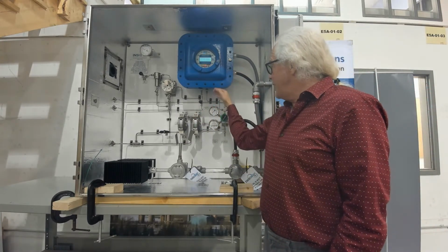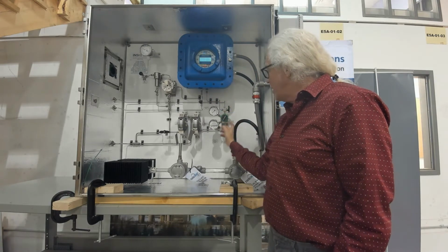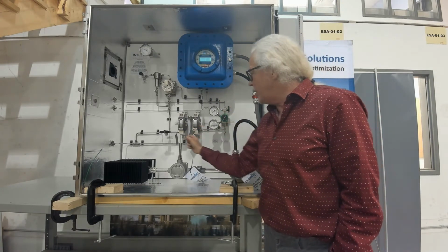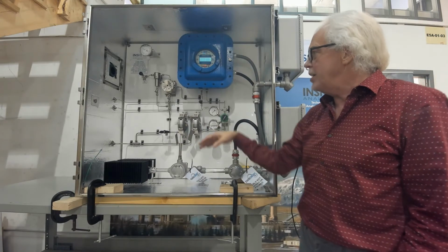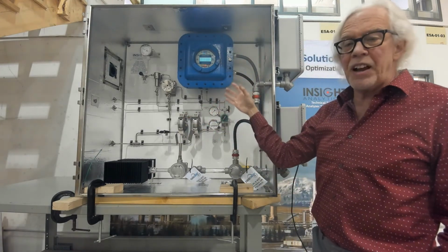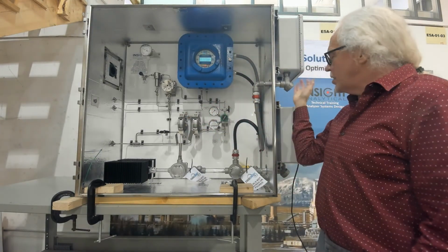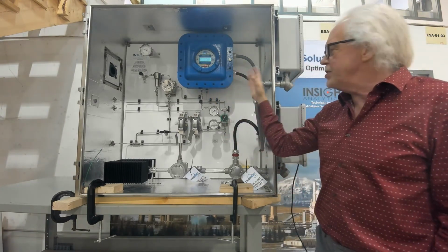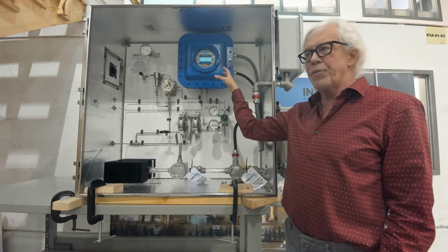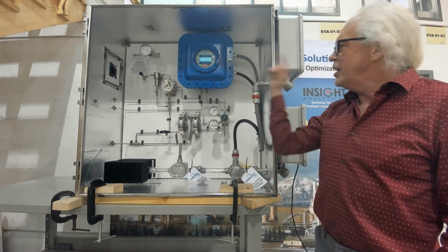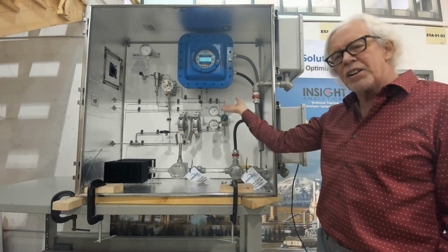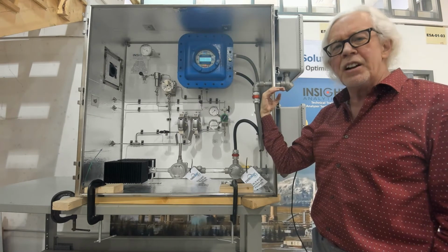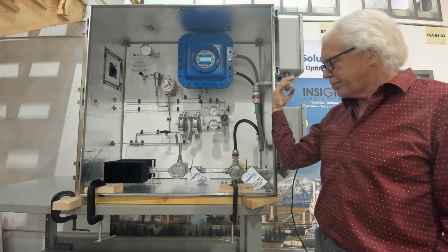The gas that vents from there is regulated down and goes to a second flow meter and goes off to our vent side. The entire package is Class 1 Div 1 on the inside, Class 1 Div 2 on the outside, supports Modbus communications, and so we have Modbus RS-485 or Modbus Ethernet communicating directly to the analyzer, sending all that information back to your DCS.